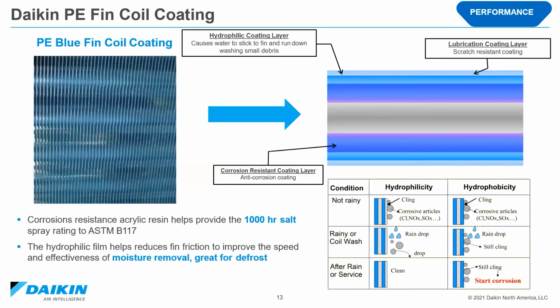The Daikin PE bluefin coating has hydrophilic properties that help reduce the fin friction along the coil. This improves the speed of the water that sticks and runs down the vertical fins, thus washing away debris and reducing the time required for defrost. Now, this acrylic resin coating also provides the 1,000-hour salt spray rating to the ASTM B117 requirements.